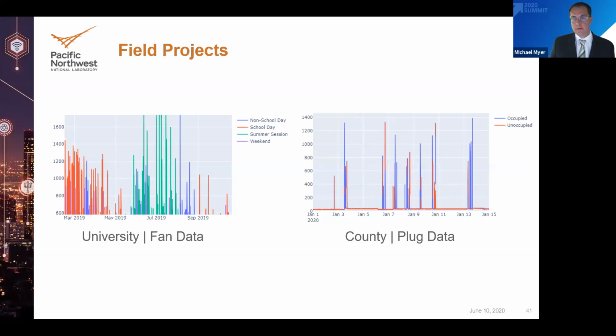Similarly, on the left, the fan data — we've programmed fans and other things based on building occupancy, but space occupancy is not the same as building occupancy. This is a university, and their building occupancy schedule is something like 7 a.m. to 9 p.m., but many of the rooms are not used that way. As a result, you can see by the significant peaks that once that space was unoccupied, the fan was able to drop out, thereby saving additional energy.